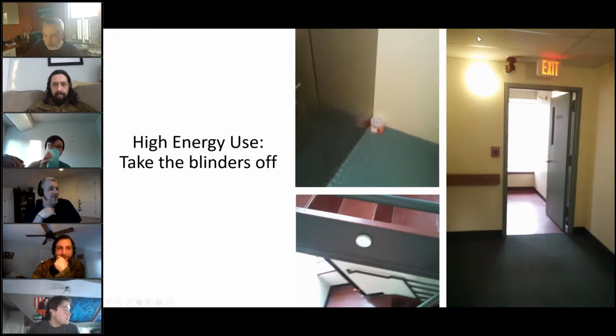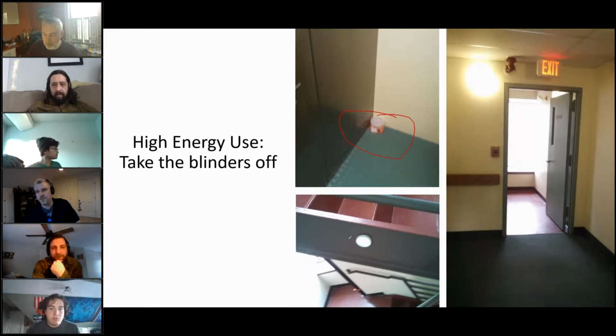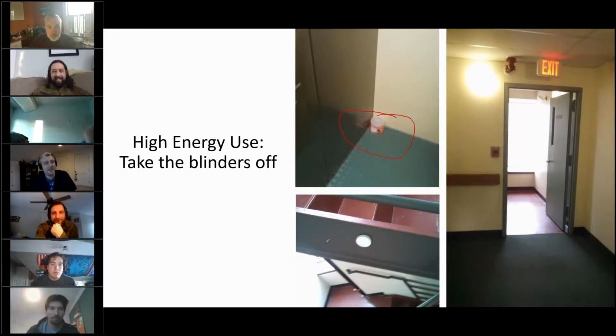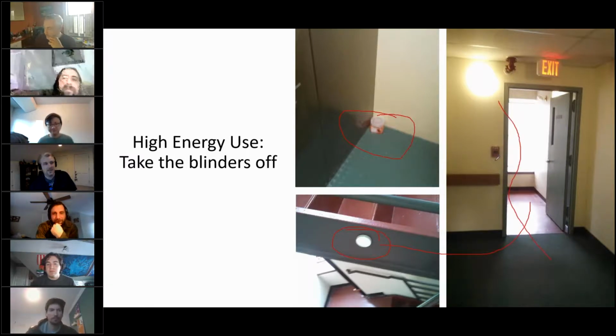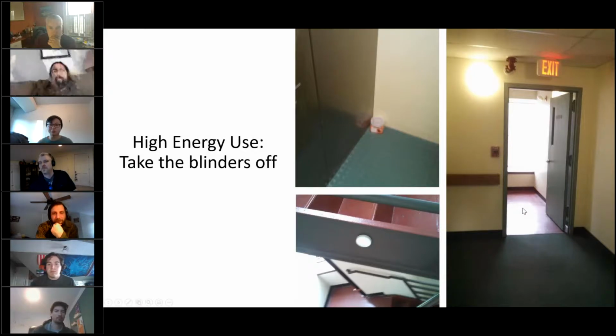Yep. So going in here, this building runs off of propane. There's a campus, there's a few mill buildings running off propane, and they have a high cost operation. So Peter came up with me one of the times, and Isaiah came up another time as well. But my first time walking in here, I noticed a few things. You walk in, and there's that big old Home Depot bucket of air fresheners. They aren't taking one air freshener out. They just cut the lid off the air fresheners and put it in the elevator. And there's air fresheners in the stairwell. And the stairwell doors are open to promote airflow through the building and make it smell a bit nicer. I'm like, there's an indoor air quality issue going on here.